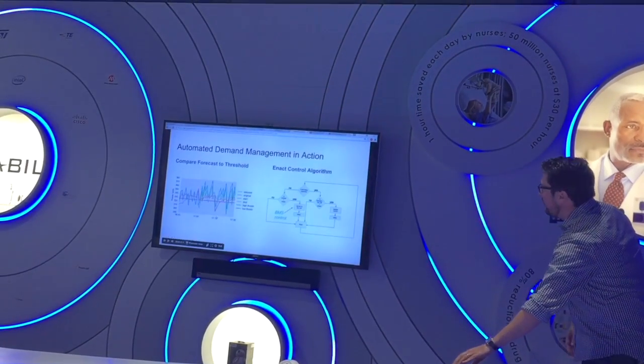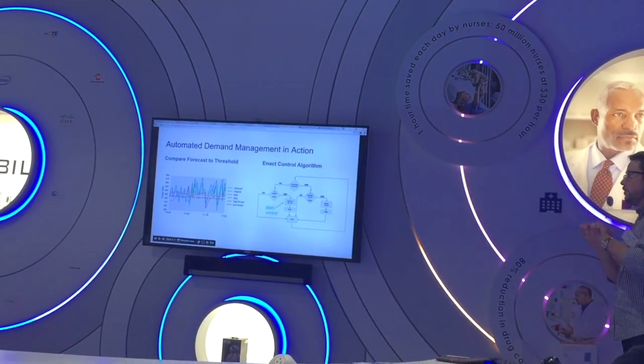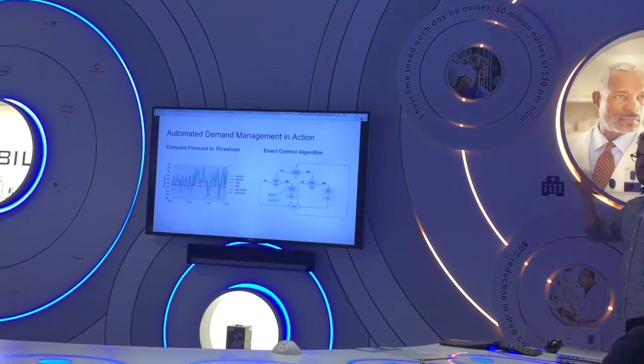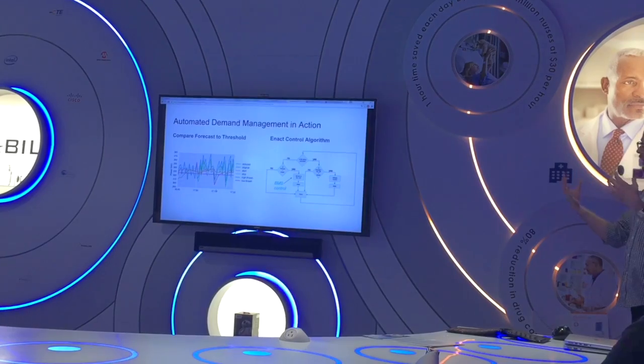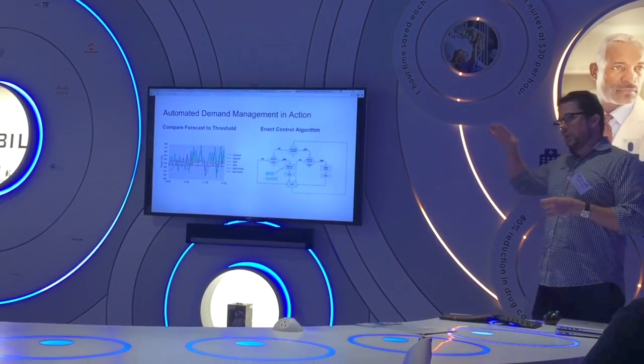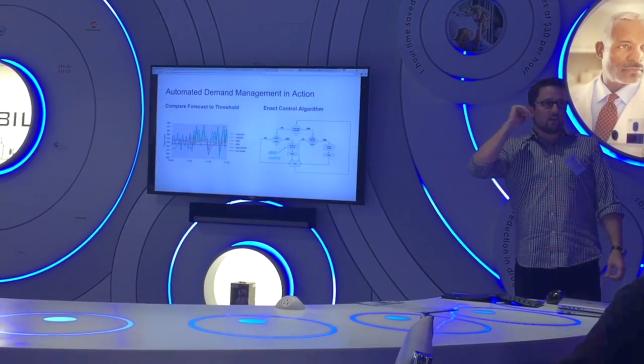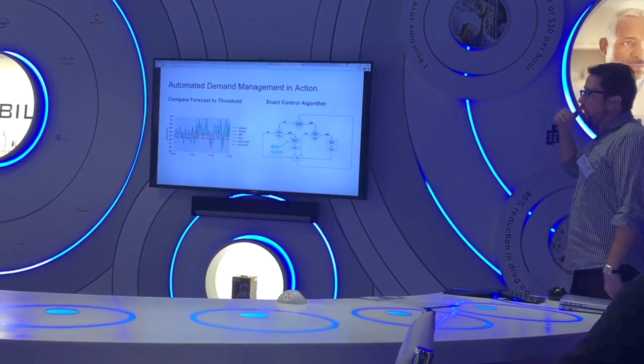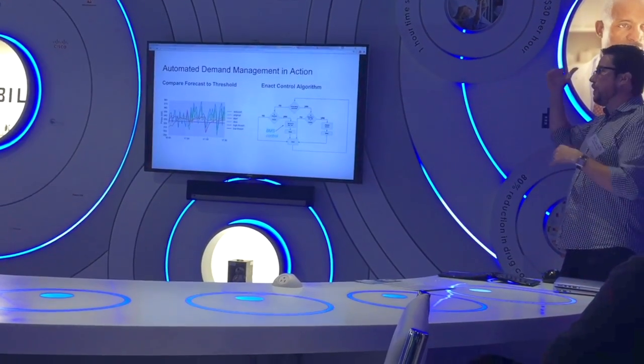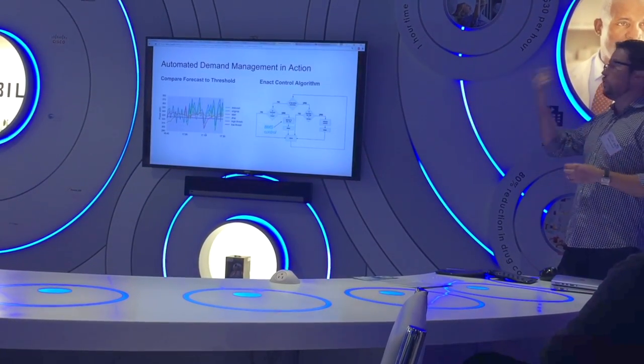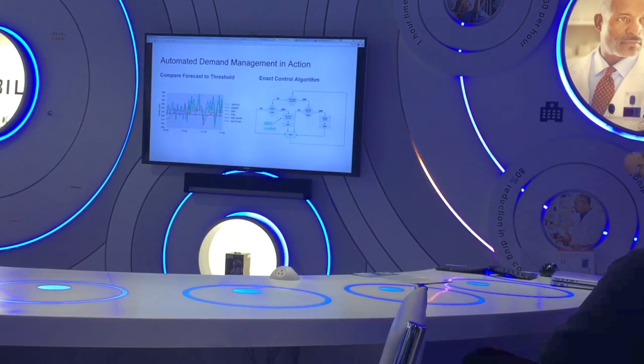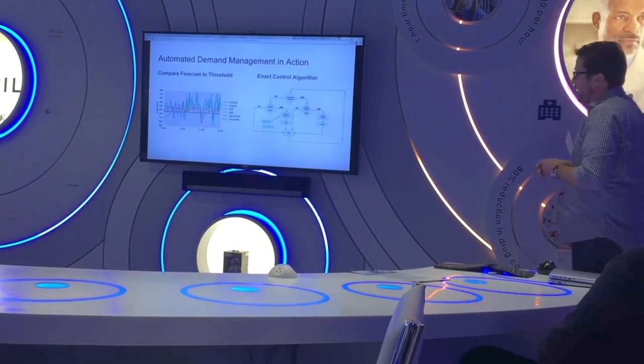And so then what we do is we compare that to the threshold, we look at all of what's happening in the building, all these different devices, how they're using energy and where the energy is going. And if we think there's a chance that we're going to cross a particular demand threshold, it's either indicative of a new billing tier or perhaps just our kind of monthly peak where it's going to charge us a super peak rate, something like that. We then set this control algorithm into action.